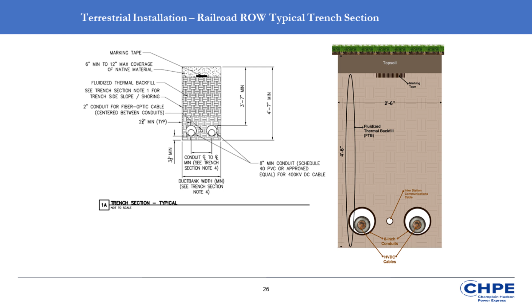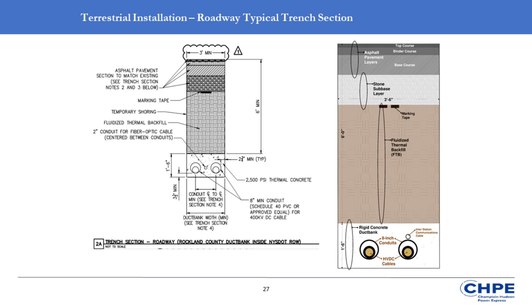Very similar on the next slide, but for an in-roadway installation. In New York State jurisdiction, most towns, villages, and counties defer to New York State specifications, which have a 5 feet minimum depth of burial under a roadway. This particular detail shows 6 feet, which is the DOT Region 8 requirement for Rockland County. All of our roadway sections include something unique: an 18-inch thick rigid concrete duct bank enclosing our conduits. From there, it's the same FTB backfill and then pavement restoration.